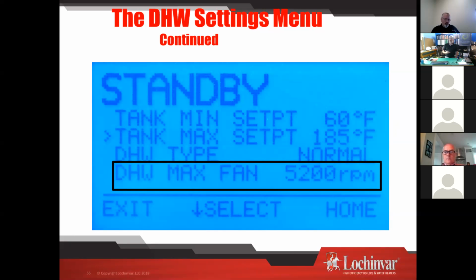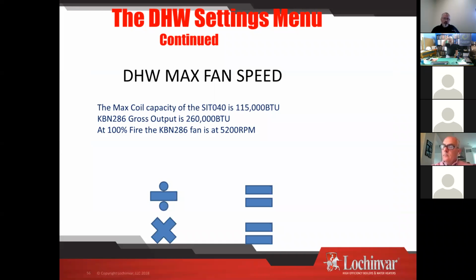So we want to slow the boiler down, and we can tell the boiler to slow down. And that's where we get into a little bit of math. I'm going to use a 40-gallon indirect and a 285,000 BTU boiler. And basically take the gross input coil capacity of the indirect and the gross output capacity of the boiler. You do a little math. So it's 44%. That's all of the boiler I need to be able to satisfy that tank. Anything other than that, the boiler is overfiring and is going to begin to cycle just because there's nowhere to dump those BTUs.